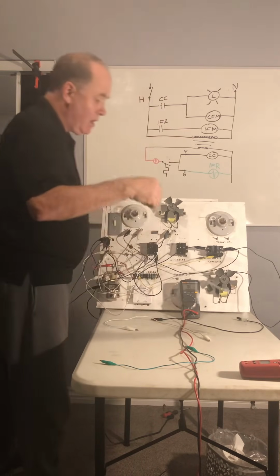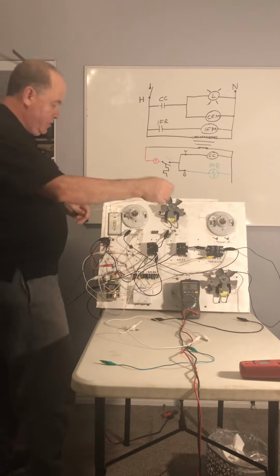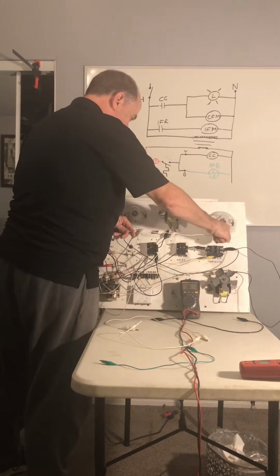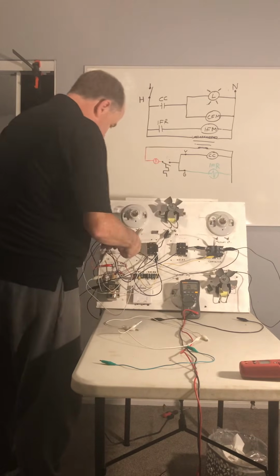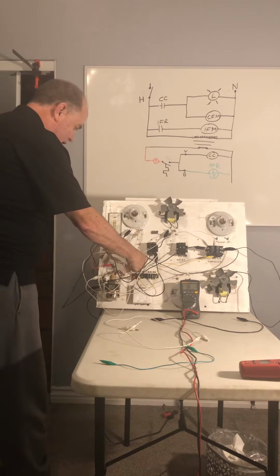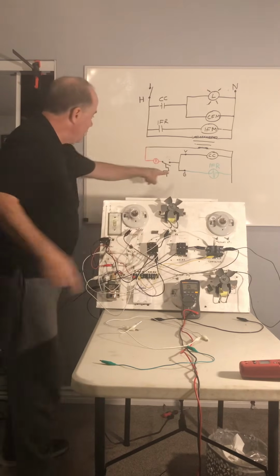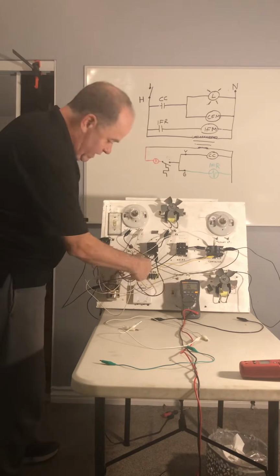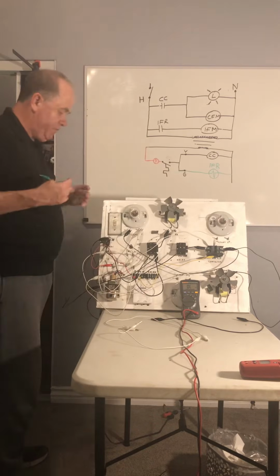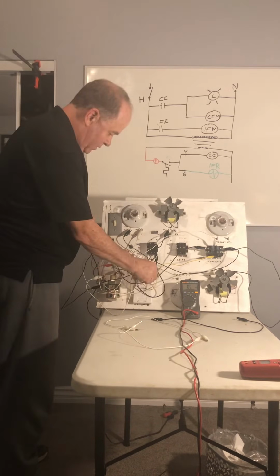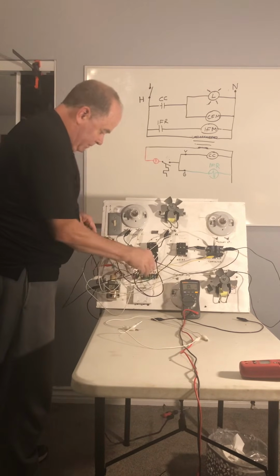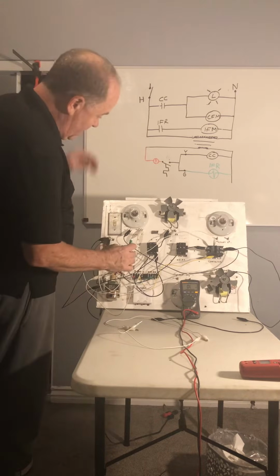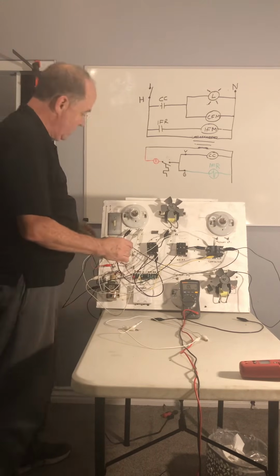And then we come back off of the other side of the contactor coil, and we go back to the secondary on the transformer. Likewise, we come off the G, or the green here, and we'll use a green wire for that to make it easier for you. And we power up the indoor fan relay coil.